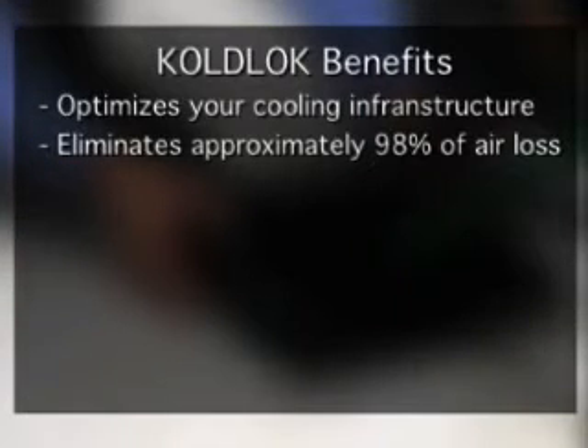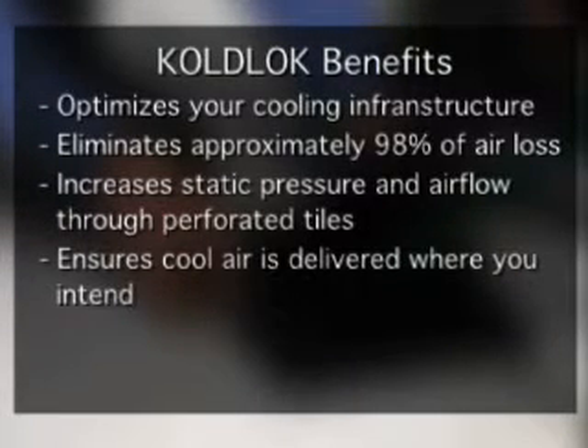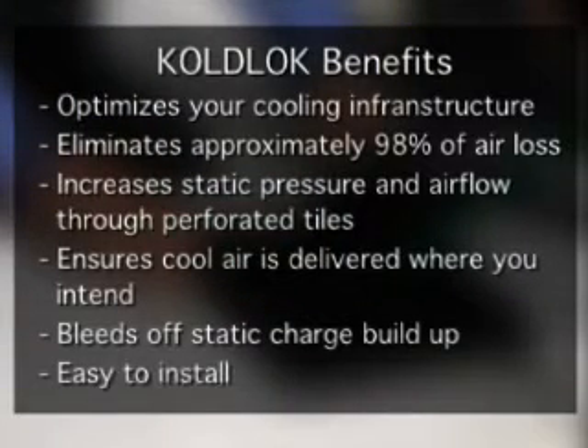To review, KoldLok raised floor grommets optimize your current cooling infrastructure, eliminate approximately 98 percent of air loss through cable cutouts, increase static pressure and airflow through perforated tiles, ensure cool air is delivered where you intended it to go, bleed off static charge buildup, and are easy to install.